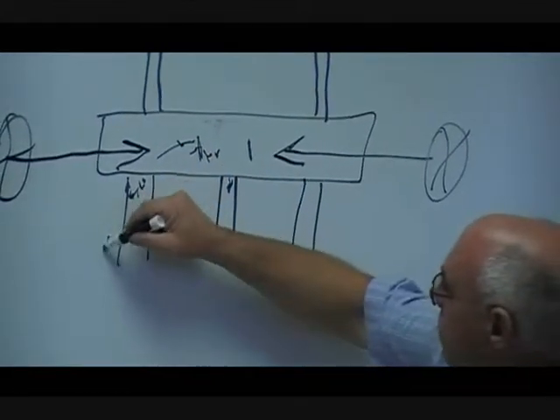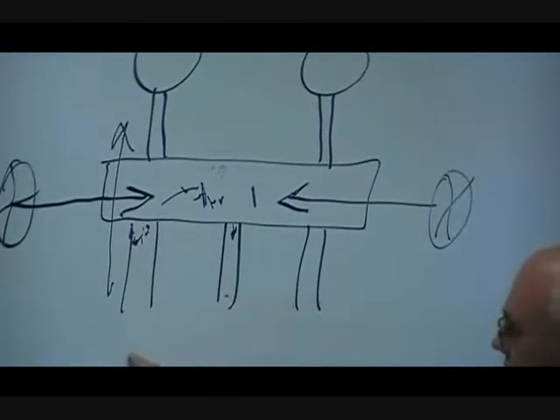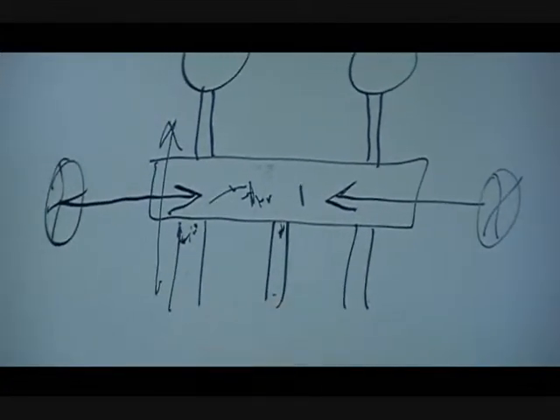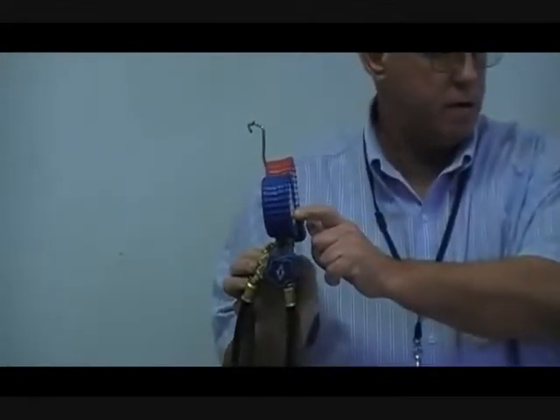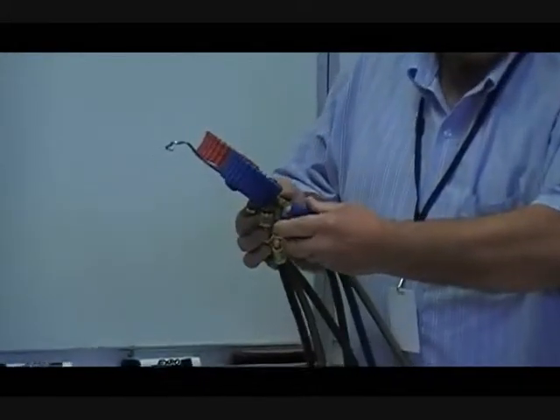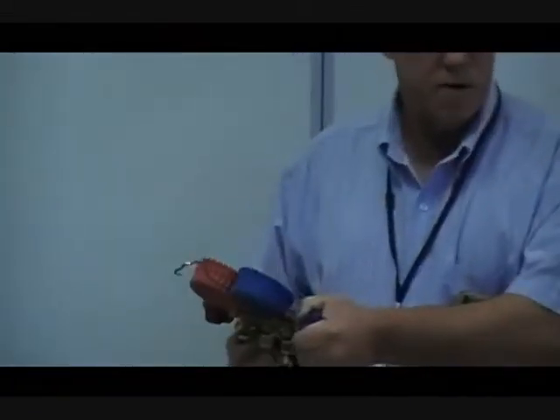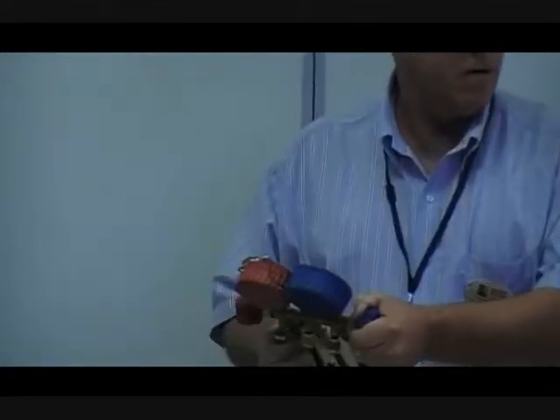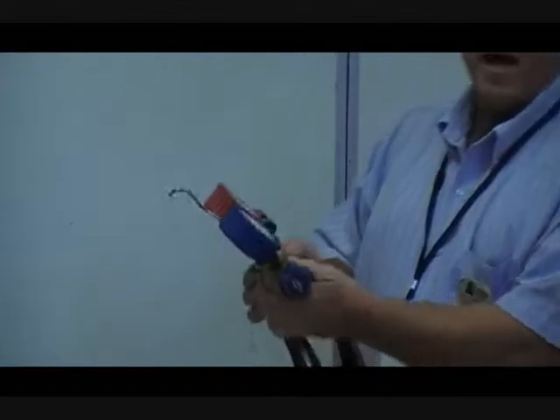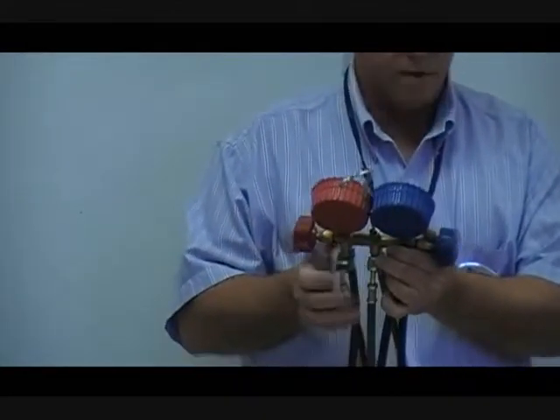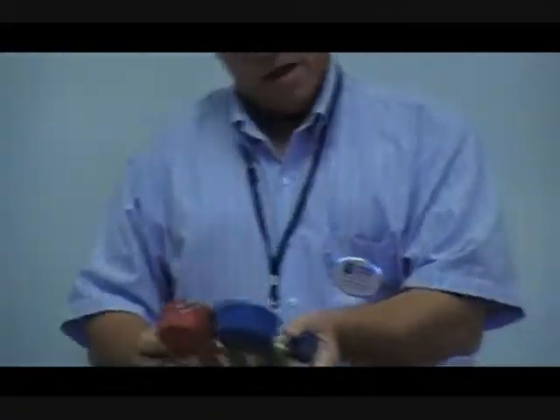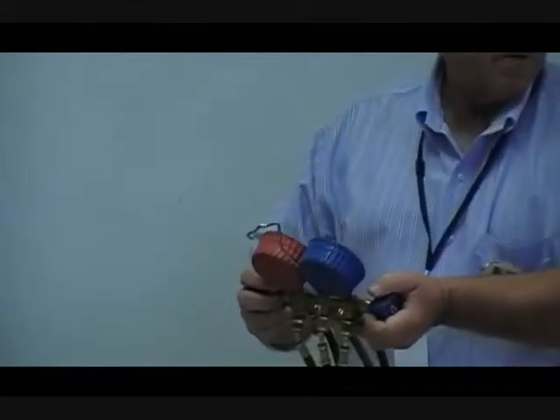It does not do anything of the pressure that's going up to the gauge. So if I've got this line hooked up to a system and I have any pressure in that system, I'm going to read pressure here. If I ask somebody to turn my gauge set off, they're going to be looking at that pressure, and they're going to close this valve. Well, this gauge is not going to move. It's still going to be measuring the pressure that's in this line. So what are they going to do? Twist on it harder, right? It still doesn't move. So what are they going to do? Twist on it even harder. You can ruin a set of gauges by doing that. You ruin the seats in there. Sometimes it's repairable, sometimes it's not. What the worst case is when you see somebody, I promise you I'm not doing this, I'm looking like I'm doing this. You can pretty well say those things are toast.